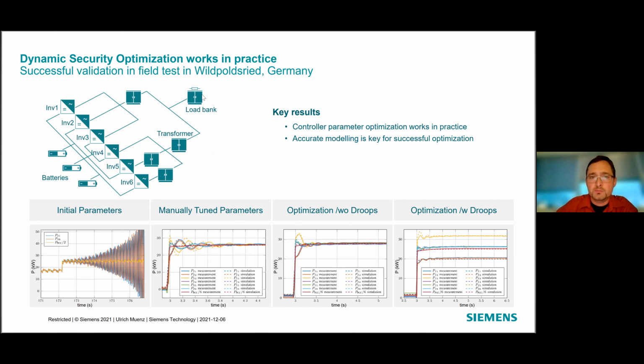Here you see the load bank. Eventually, when we were operating the feeder, it was actually a small feeder with real customers—real households, a supermarket, and so on. This was a preliminary test we did to understand parallel grid forming of these inverters. These are commercial Siemens Dynamics inverters, but I think the effects we see would be similar with other inverters.